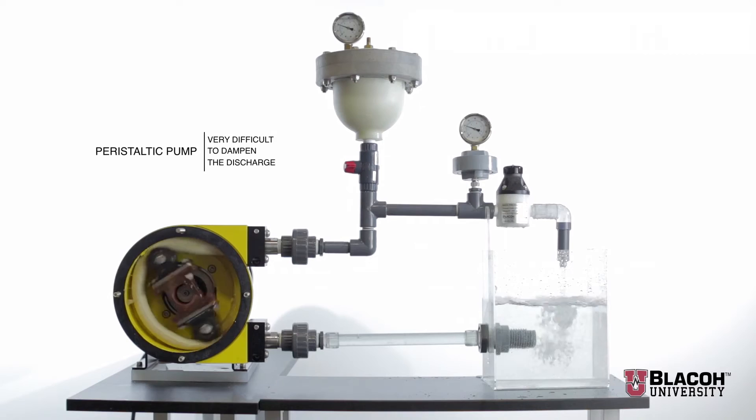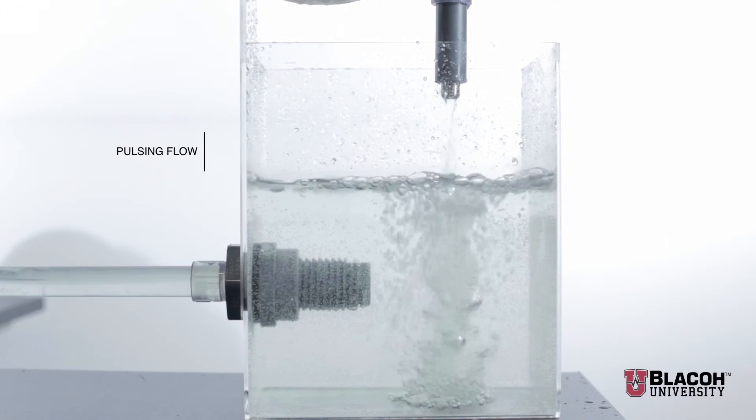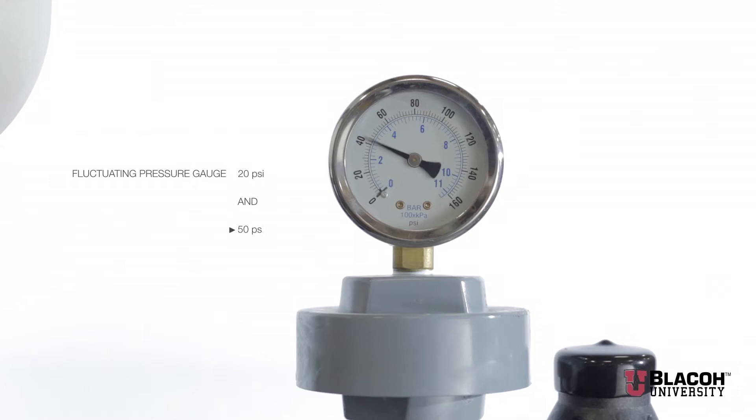You will notice that the flow is pulsing as it comes out of the discharge and that there is a very large swing in pressure on the pressure gauge. The flow actually stops at every rotation of a roller shoe.